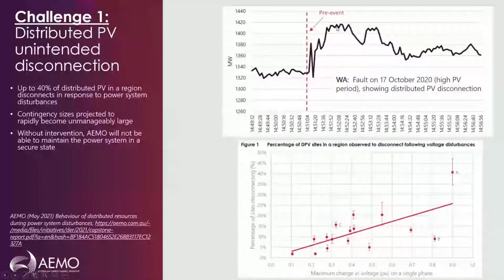This bottom chart here is showing data that we've got from a company called Solar Analytics, who have third-party monitoring on rooftop PV systems. They now have coverage of tens of thousands of systems across the NEM, and we've looked at the percentage of sites that we see disconnecting in power system disturbances across the grid. This is plotted as a function of the minimum voltage recorded on a single phase, to give an indication of how severe the fault was. You can see that in these more severe disturbances, we're seeing quite large amounts of PV tripping off, up to around 40% in the worst case that we saw here. But more typically around 10 to 20% of PV systems tripping off for milder faults.